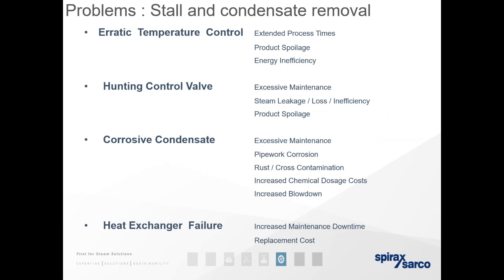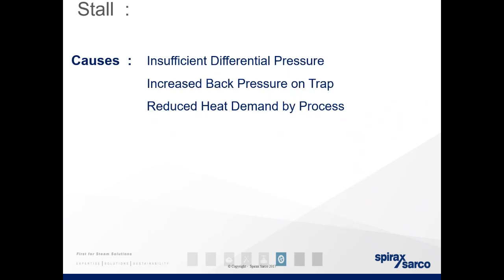Rust, cross-contamination, so in your strainers, if you're starting to see process media in your strainers, or you're seeing excessive rust particulates, and increased chemical dosage costs, increased blowdown because you have more particulates, and increased maintenance, downtime, and replacement costs on heat exchangers. So as it says here, causes: insufficient differential pressures, so the steam isn't being pulled through the system properly. Increased back pressure on the trap, so you're unable to clear as much condensate as you require, leading to the filling of coils, or of heat transfer processes like a heat exchanger. Reduced heat demand by process, so effectively that's a little misleading, that statement, but it's effectively taking longer to heat up your process.